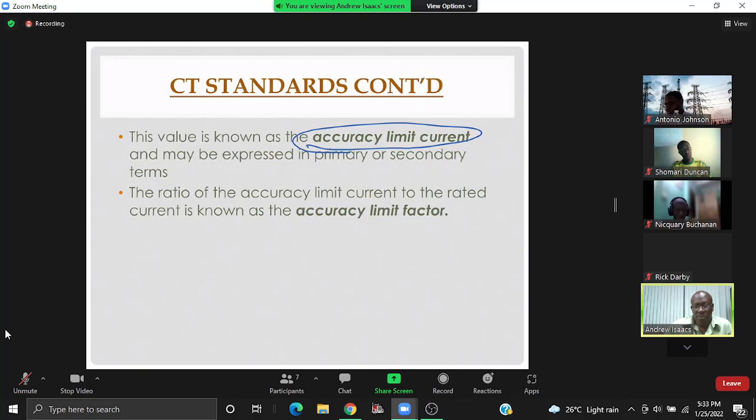And then, of course, the accuracy limit current to the rated current, that ratio, yes, is known as the accuracy limit factor. Because we're dealing with an electromagnetic device, it will provide accuracy up to a point. And that limiting point, from a current standpoint, is known as the accuracy limit current.